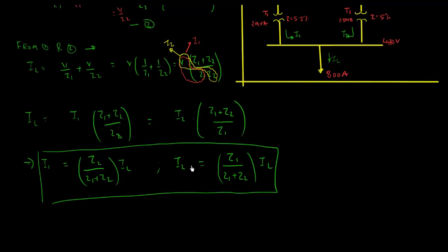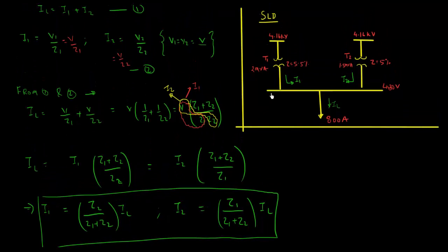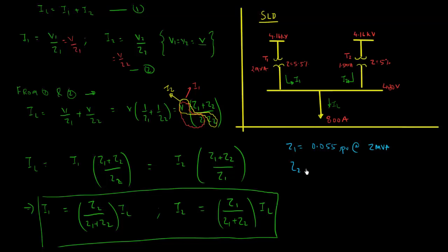The reason we can't substitute directly is that Z1 and Z2 are on different bases. In per-unit analysis, all impedances must be on the same base. We have Z1 = 0.055 per unit at 2 MVA, and Z2 = 0.050 per unit at 1.5 MVA. We need to convert one to match the other's base.